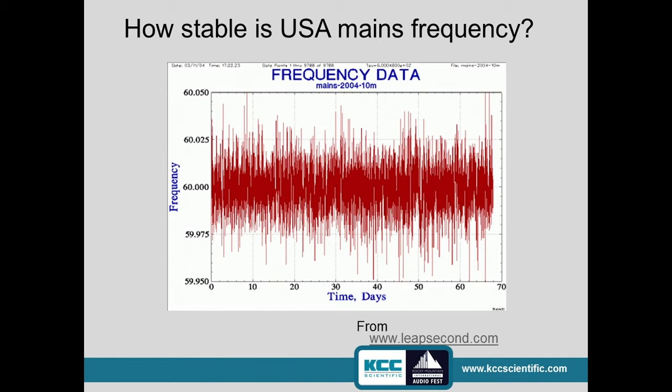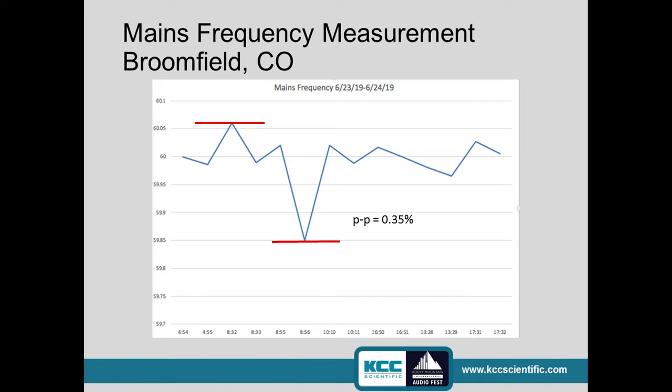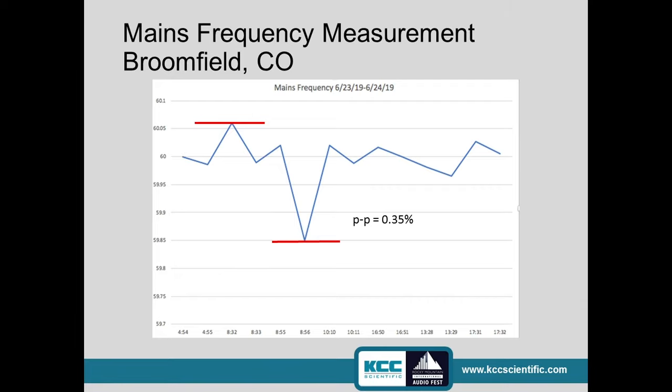So how stable is the frequency in the US? This data is taken from leapsecond.com, which monitored frequency over a period of several days — you can see the peaks and valleys for yourself. I took a few points in Broomfield, Colorado, and over about a 24-hour period I observed about 0.35% peak-to-peak change. That's noticeable. That's real speed change.